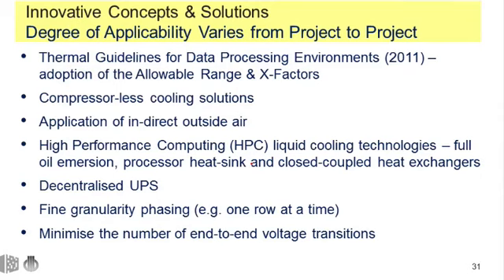Compressorless cooling solutions are becoming more commonplace, fundamentally driven by moving towards supply air control and the adoption of the recommended and allowable ranges. We've seen within certain areas of Europe in particular, we don't even enter into the allowable range with the right supply air control strategy, and that's with compressorless cooling solutions. One of the obvious benefits there is not just the OPEX savings that are associated with it, but also the CAPEX savings with respect to the downsized electrical infrastructure. The application of indirect outside air has certainly gained traction with some evaporative cooling.